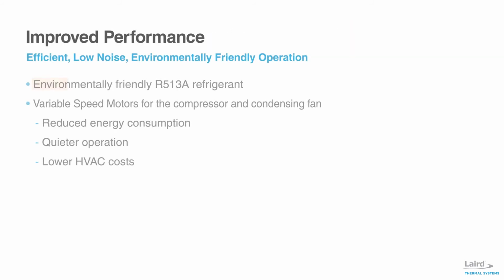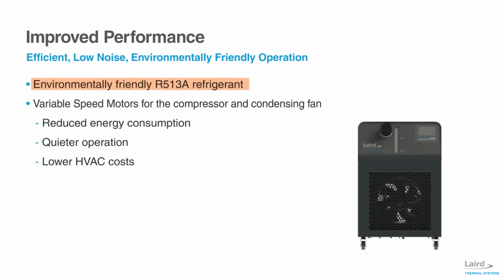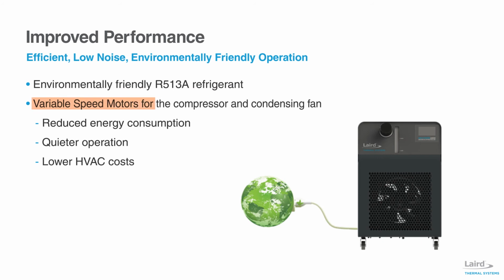By using environmentally friendly 513A refrigerant, the Nextreme Chiller delivers similar performance with half the global warming potential compared to traditional hydrofluorocarbon refrigerants. Users will also benefit from the variable speed motors for the compressor and condensing fan, which result in a quiet operation and improved energy efficiency. This also introduces less heat into the environment, lowering HVAC costs.